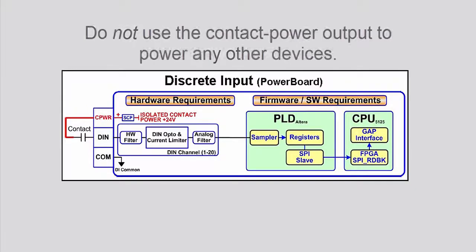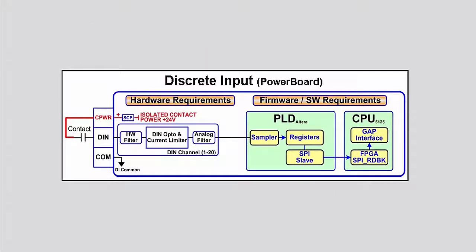This supply includes short circuit and over voltage protection. Do not use the contact power output to power any other devices. The contact output power on pins 21, 22, and 23 can supply up to 150 milliamps maximum. If desired, an external 16 to 32 volt DC power source can be used for the circuit.